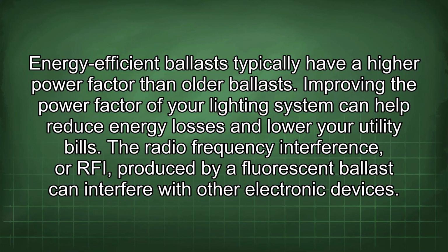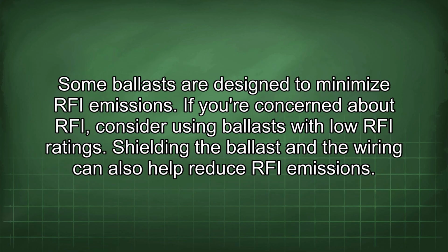The radio frequency interference, or RFI, produced by a fluorescent ballast can interfere with other electronic devices. Some ballasts are designed to minimize RFI emissions. If you are concerned about RFI, consider using ballasts with low RFI ratings. Shielding the ballast and the wiring can also help reduce RFI emissions.